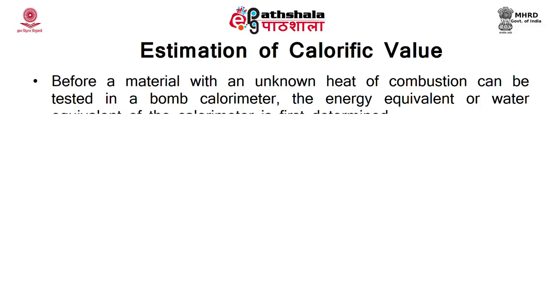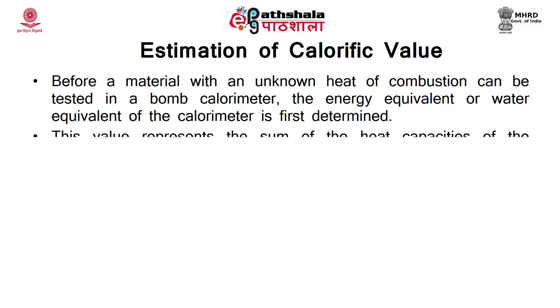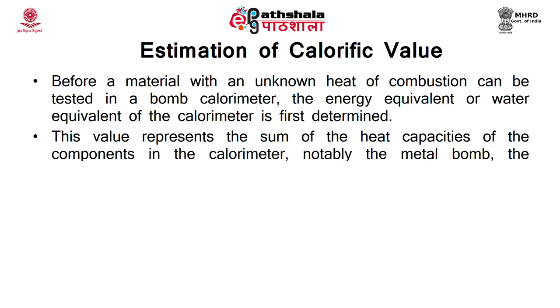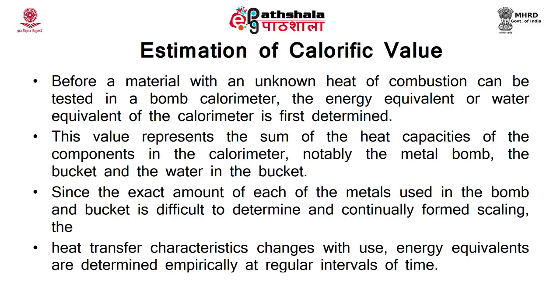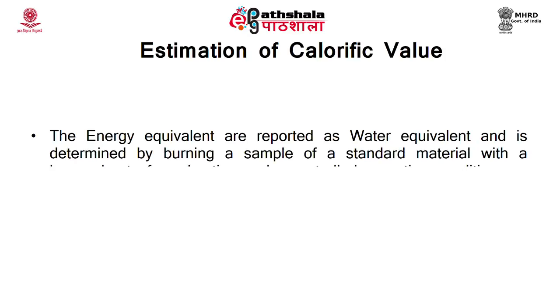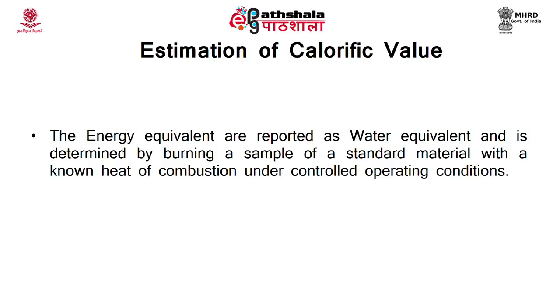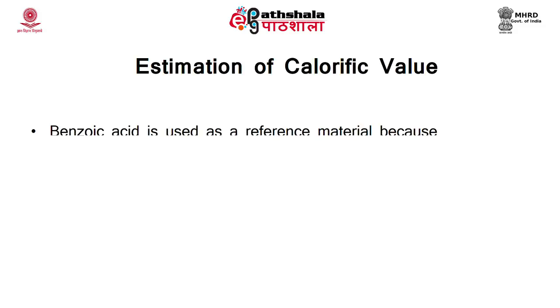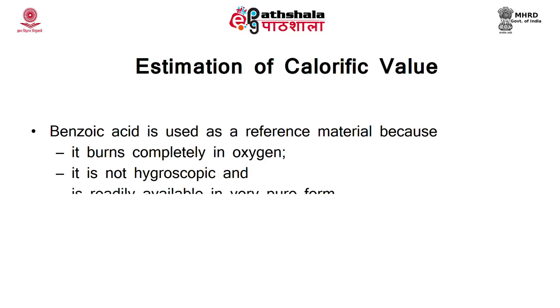Before a material with unknown heat of combustion is tested, the energy equivalent — also called water equivalent — of the calorimeter is first determined. This value represents the sum of heat capacities of the components: the metal bomb, the bucket, and the water. Since the exact amount of each metal is difficult to determine and heat transfer characteristics change with use, the energy equivalent is determined empirically at regular intervals. The energy equivalent is determined by burning a standard material with a known heat of combustion under controlled conditions. Normally benzoic acid is used as reference material because it burns completely in oxygen, is not hygroscopic, and is readily available in very pure form.